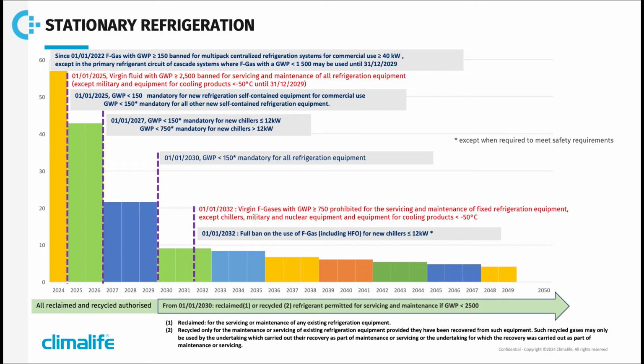We will not be able to use virgin refrigerant with a GWP greater than 750 for the maintenance of fixed refrigeration, except for exemptions again, and the use of F-Gas, including HFO, will no longer be accepted for chillers up to 12 kilowatts, except in the case of safety requirements. I remind you once again, from 2027, the Commission will study the evaluation reports every 3 years before revising the F-Gas in 2040. So to conclude, solutions with GWP less than 150 are the standard to be achieved as quickly as possible.